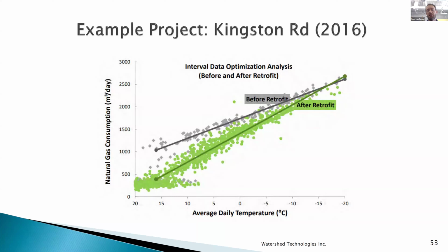And this is an example of that initial plot I showed before, where you have that big overhead initially around the balance temperature. After the retrofit, we see a more gradual transition from summer conditions, where you're heating just domestic hot water. And when you turn on your space heating, you now have a smooth transition instead of that big jump in gas consumption.